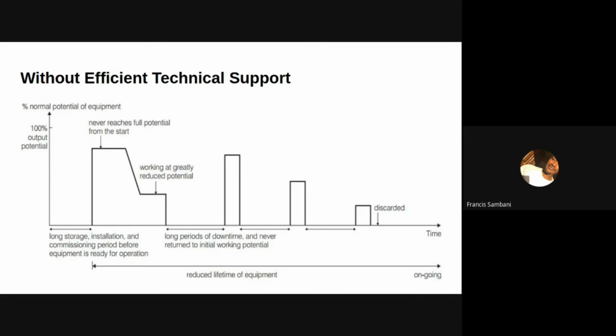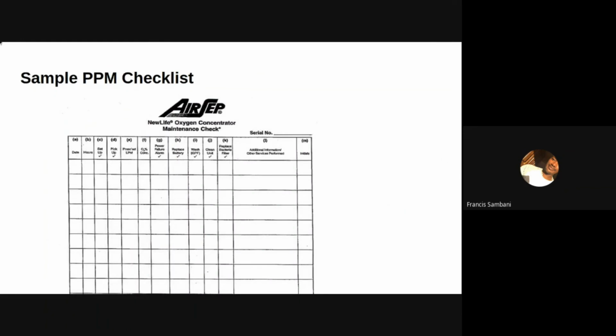And if we look at the next slide, I don't think it's visible on your end. But this is just a maintenance checklist for a monthly inspection that you can use. So you have a date in the first column, and then you have the hours. The hours you get from the Hobbs meter or the hour meter. And then you have a percentage oxygen concentration. So every time you do a check, you must write down the percentage oxygen concentration.